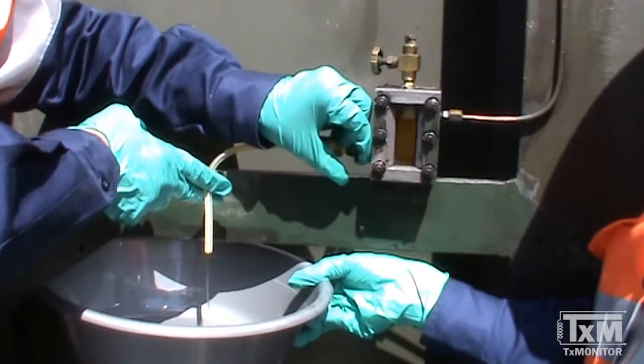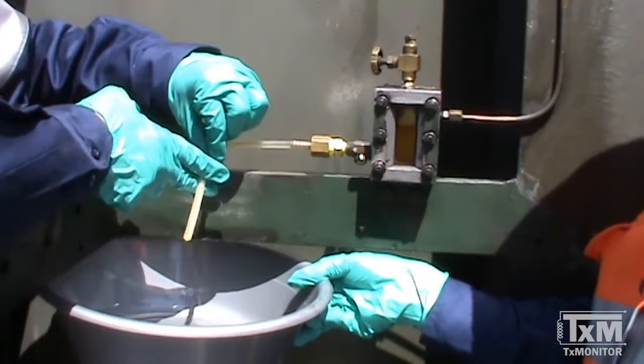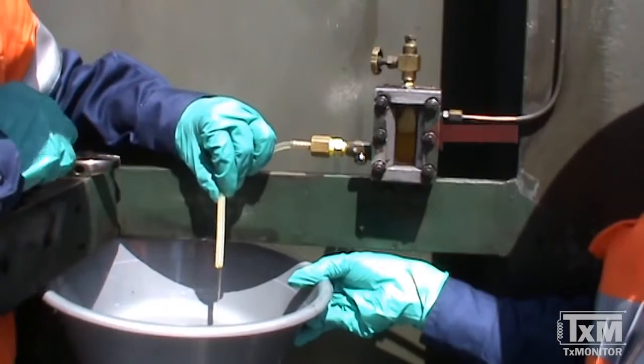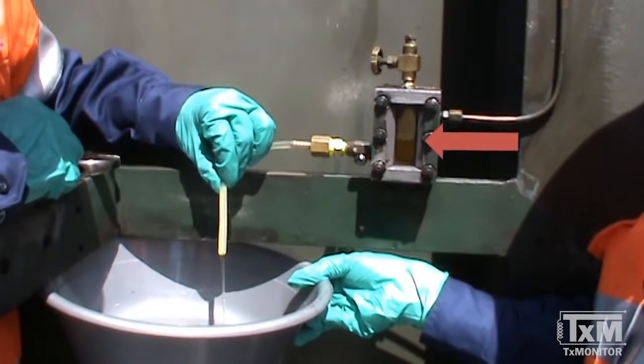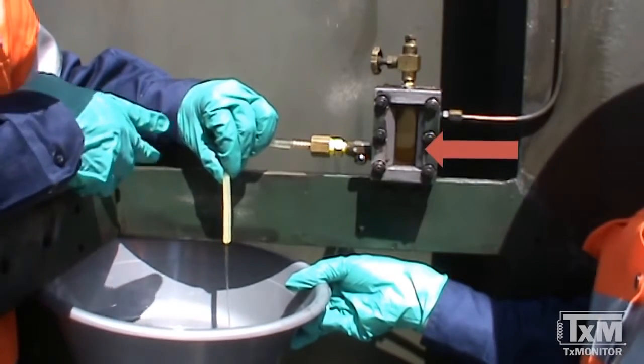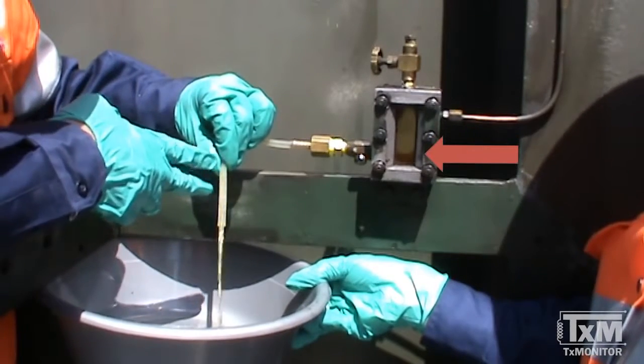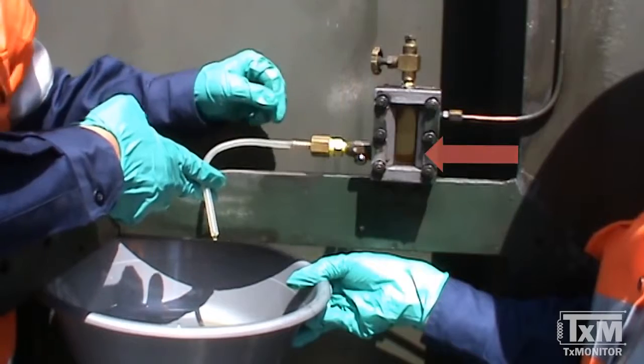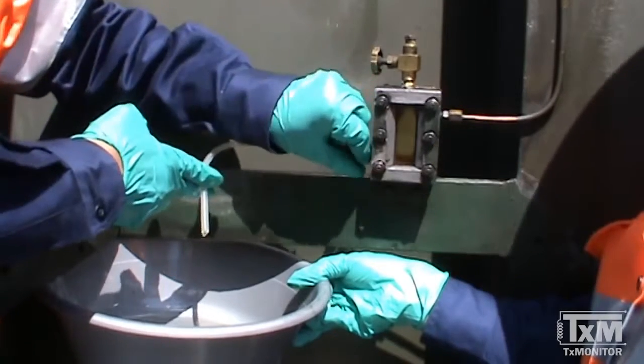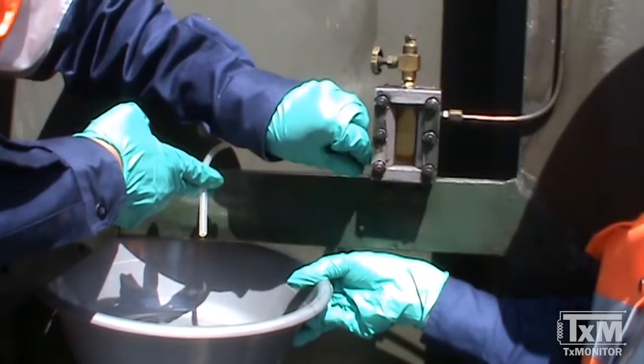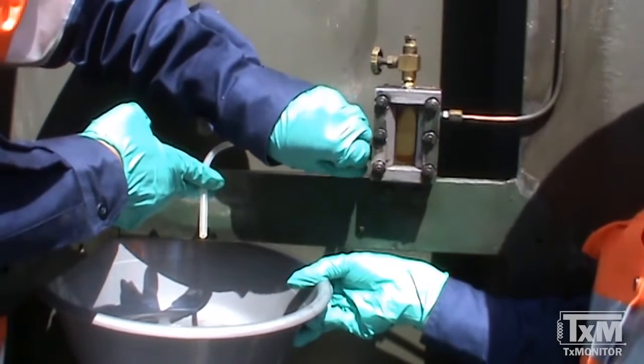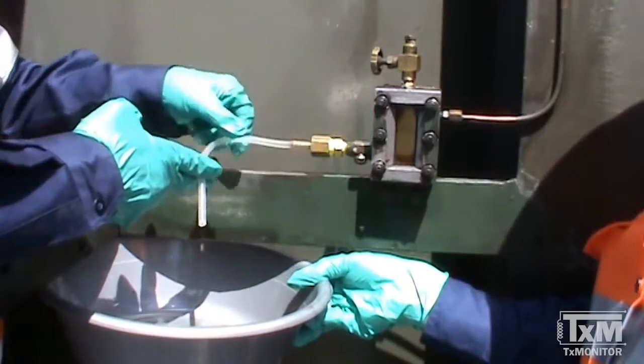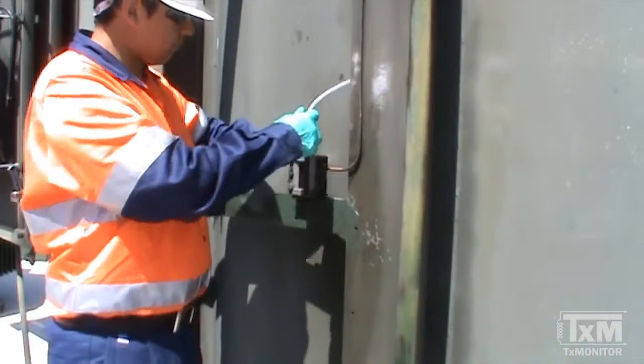Open the bottom port of the sampling device and allow the oil to drain. You will notice that the oil level in the sampling device decreases. Once the sampling device is full of gas, close the bottom port. Once the gas is collected in the sampling device, retrieve the gas by following the next steps.